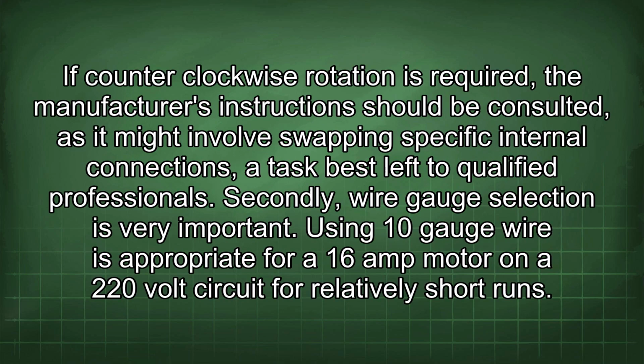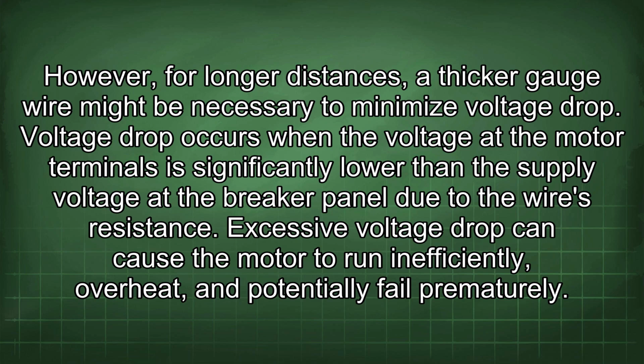If counterclockwise rotation is required, the manufacturer's instructions should be consulted, as it might involve swapping specific internal connections, a task best left to qualified professionals. Secondly, wire gauge selection is very important. Using 10-gauge wire is appropriate for a 16-amp motor on a 220-volt circuit for relatively short runs. However, for longer distances, a thicker gauge wire might be necessary to minimize voltage drop.